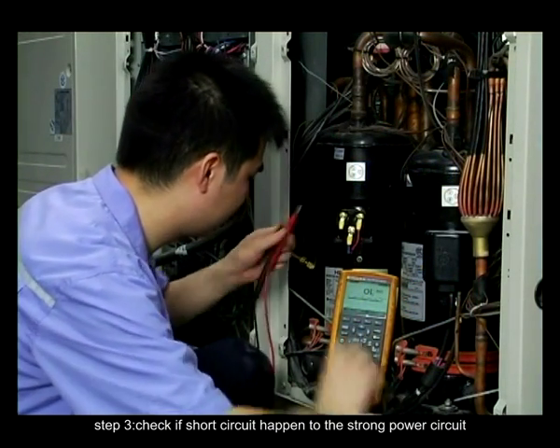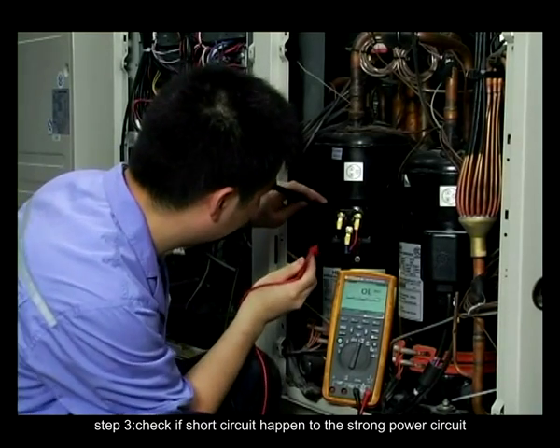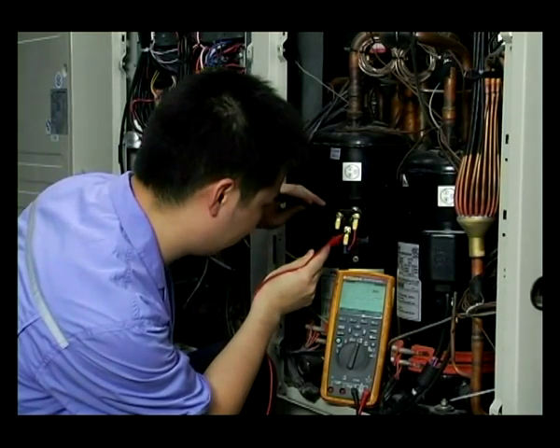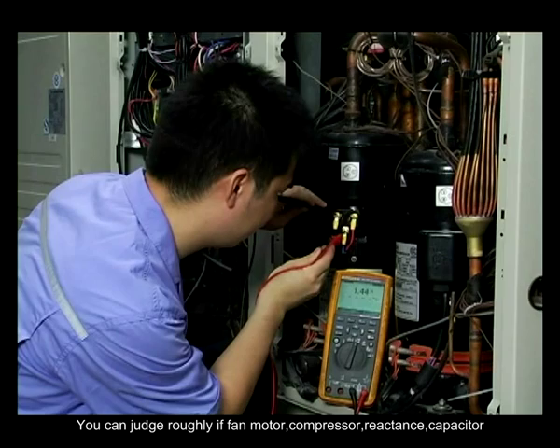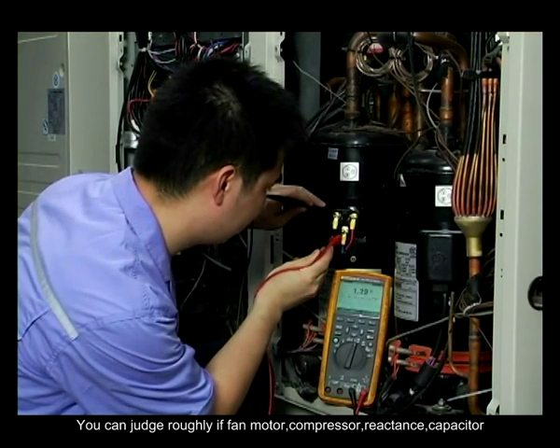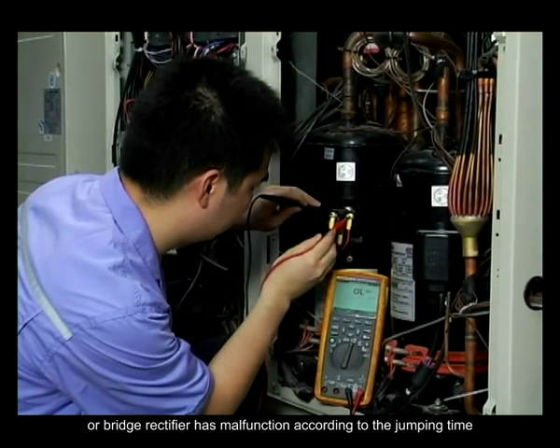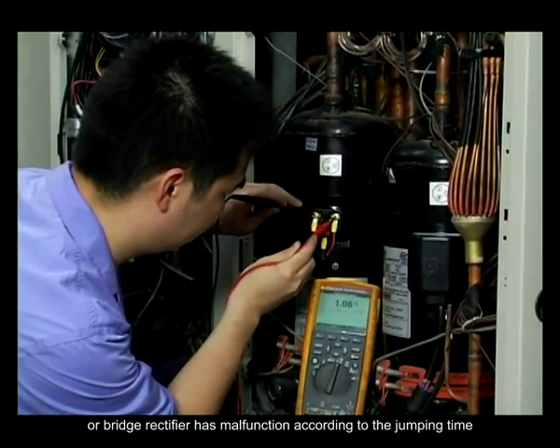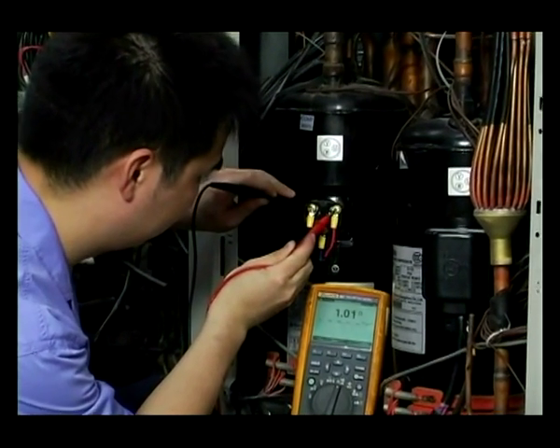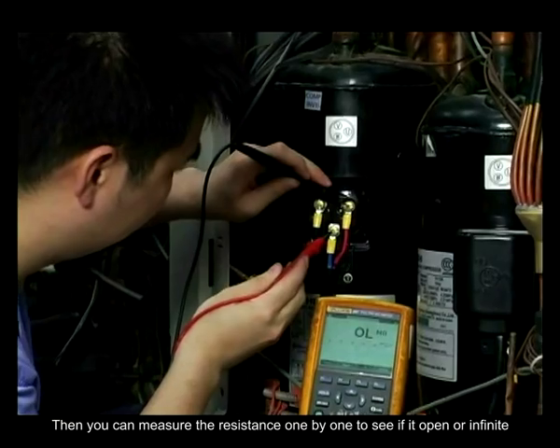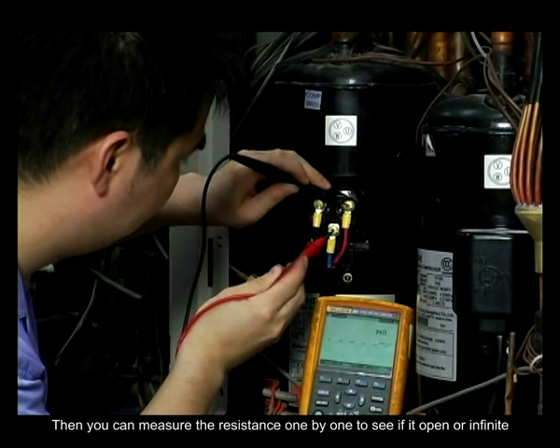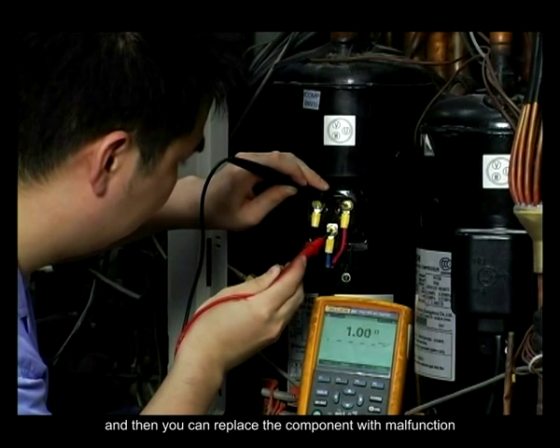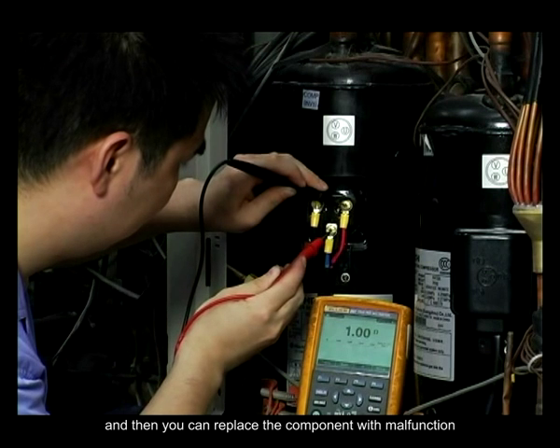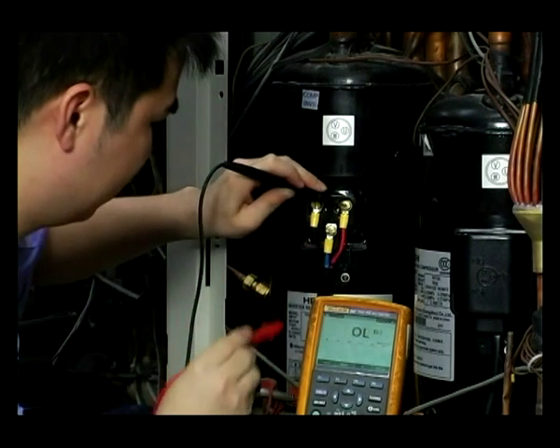Step 3. Check if a short circuit happens in the strong power circuit. You can judge roughly if the fan motor, compressor, reactance, capacitor, or bridge rectifier has malfunctioned according to the jumping time. Then you can measure the resistance one by one to see if it is open or infinite, and then replace the malfunctioning component.